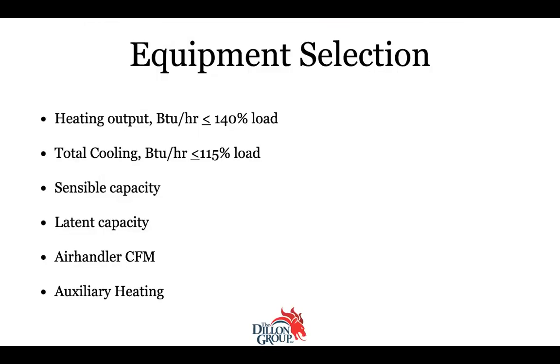When it comes to equipment selection, they look at the heating output in BTUs per hour, and you're trying to get the heating to be less than or equal to 140% of the load. So they already build in, not only is it oversized 99% of the time, but they have this allowable margin of excess capacity, because you're never going to find a system that delivers exactly what the load calls for. So for heating and cooling, they give you these kinds of variances. And you have to look at the sensible capacity, the latent capacity, and the air handler CFM, the airflow through the air handler. And you also have to look at the auxiliary heating that got put in.